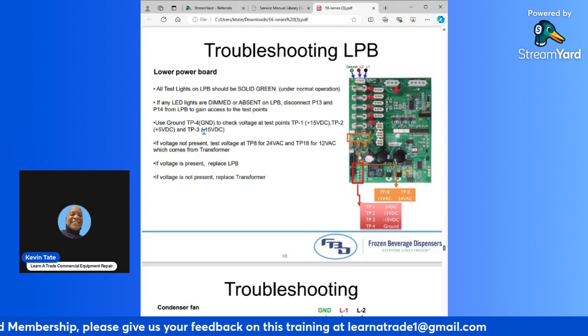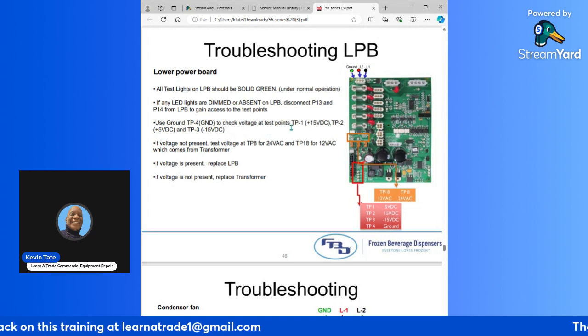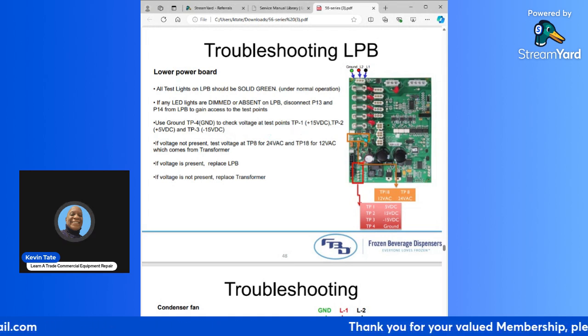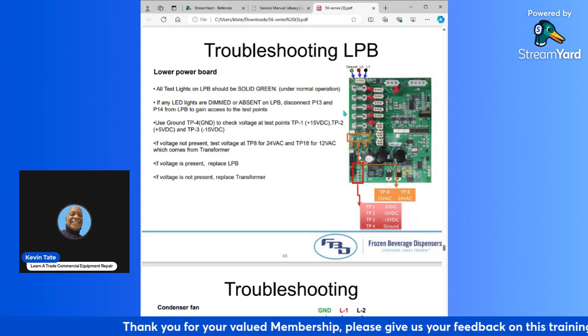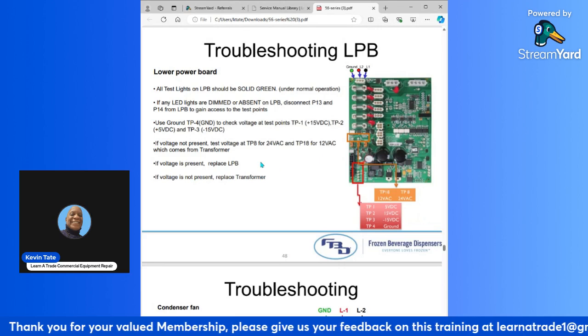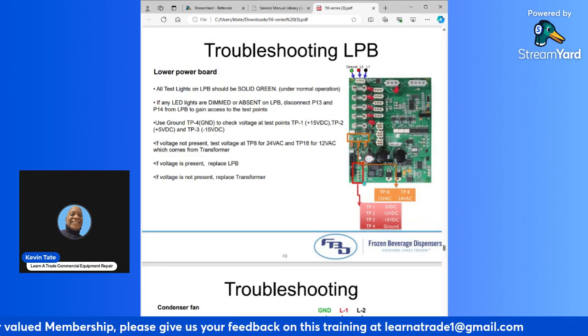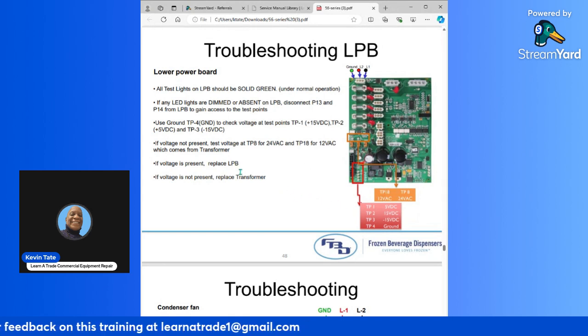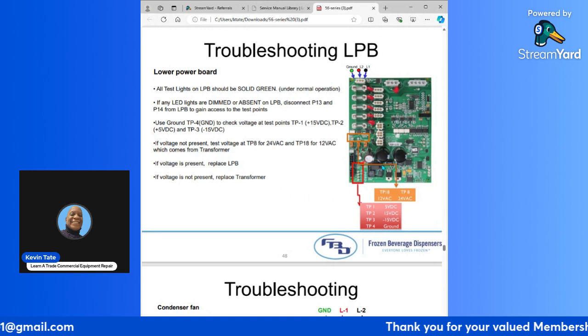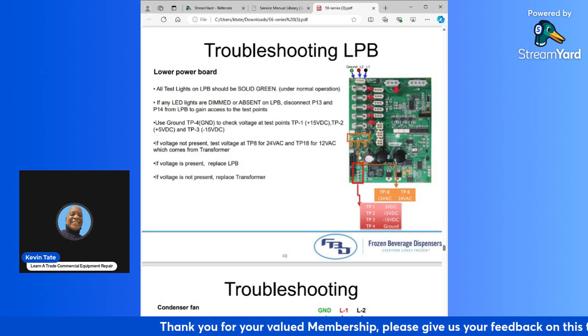Use ground, TP4 ground, to check voltage at test points. So you're going to go to the TP4 position on the board as your ground. You're going to use that as your ground, and then you will be able to test all of your test points if you needed to, if you didn't have any LEDs that were on, or if you had LEDs that were out. This will enable you to find out what functions are not working.